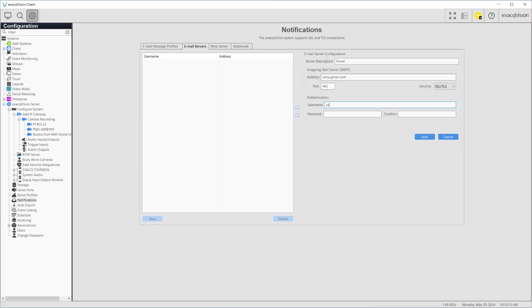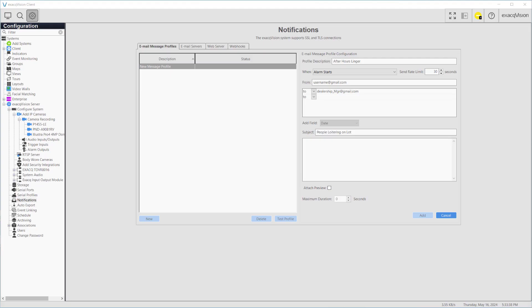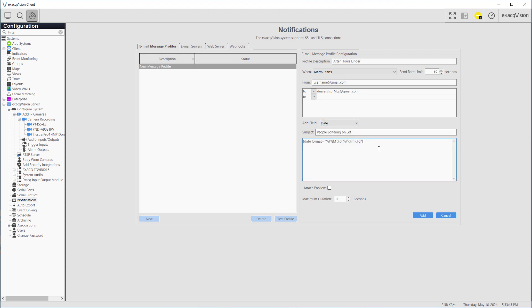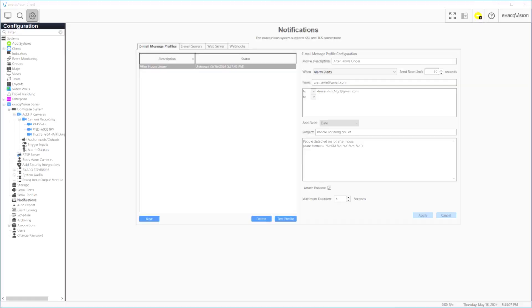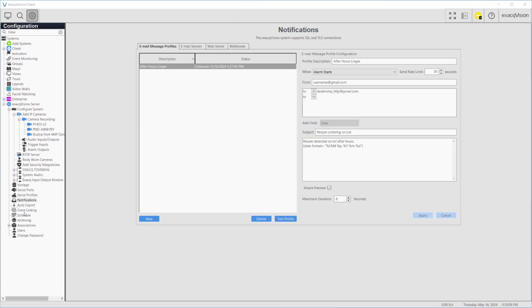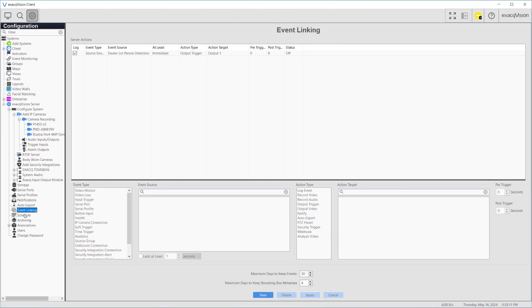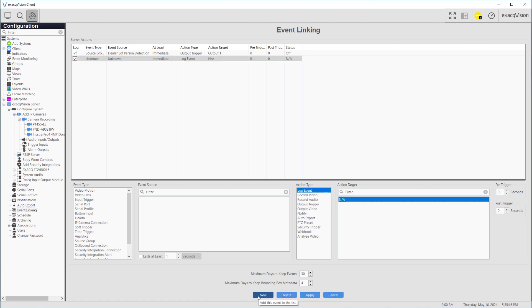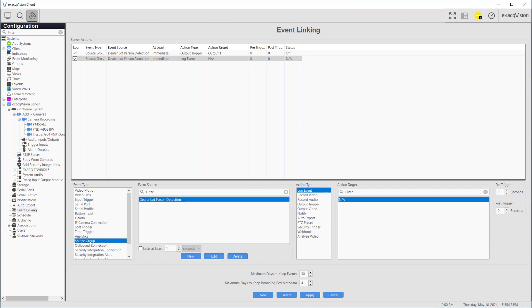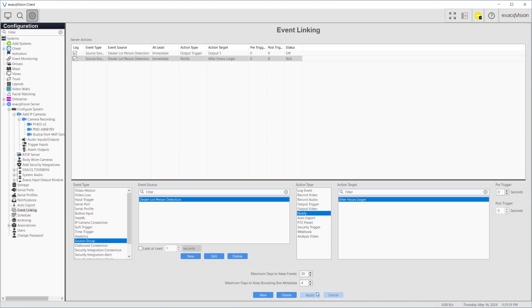The second part of our scenario requires sending a notification to a staff member of the car dealership. Using the Notifications page Email Servers tab, we must first add an SMTP server to the system. Next, using the Email Message Profiles tab, we create an email profile which includes the To and From addresses as well as the message to be sent. Refer to the user manual or user training videos on notification configuration for more information. With the notification configured, we head back to the Event Linking page. Press the New button. We can now save time and keep our event linking list as tidy as possible by reusing our previously created source group from the Event Type and Source panels. This time our Action Type will be Notify, with the Action Target being the name of the email message profile we just created. A final test confirms that our audio message is played from the speakers and our notification message was successfully sent to the employees or owner of the facility.